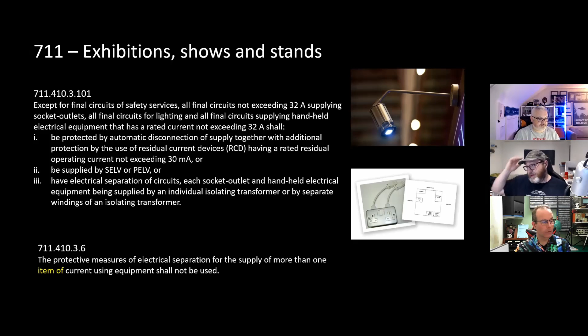That's a comment I've got to make after this. There's a couple of words I think missing from that regulation. Not surprised, this is an old reg. So the TN system basically says we don't want to use PME. PME is not suitable for exhibition shows and stands unless continuously supervised by skilled or instructed persons and the suitability and effectiveness have been ascertained.